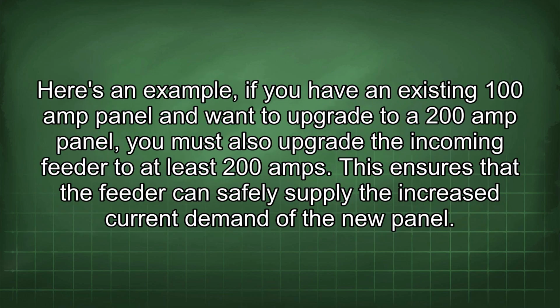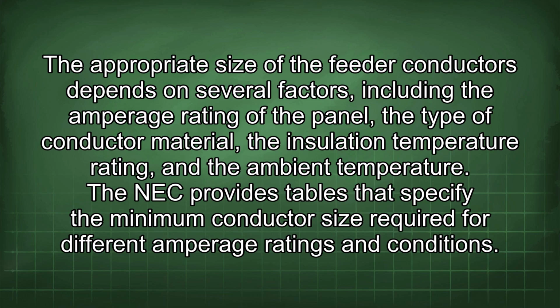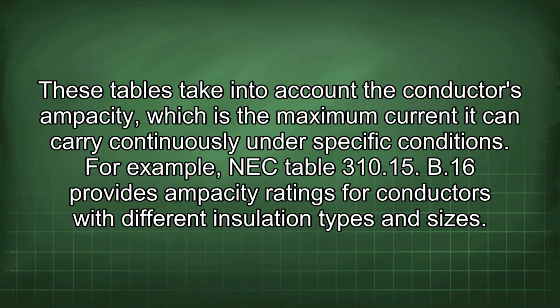Here's an example. If you have an existing 100 amp panel and want to upgrade to a 200 amp panel, you must also upgrade the incoming feeder to at least 200 amps. This ensures that the feeder can safely supply the increased current demand of the new panel. The appropriate size of the feeder conductors depends on several factors, including the amperage rating of the panel, the type of conductor material, the insulation temperature rating, and the ambient temperature. The NEC provides tables that specify the minimum conductor size required for different amperage ratings and conditions. These tables take into account the conductor's ampacity, which is the maximum current it can carry continuously under specific conditions.